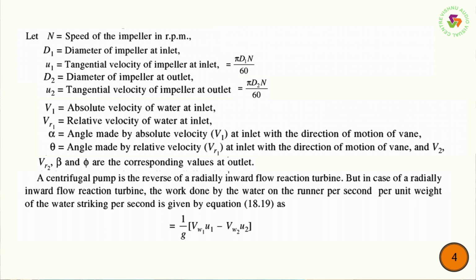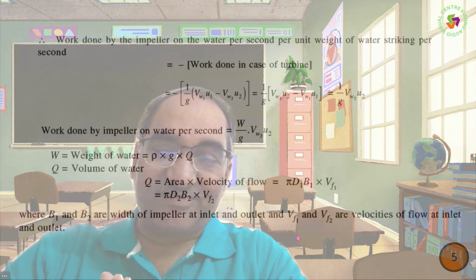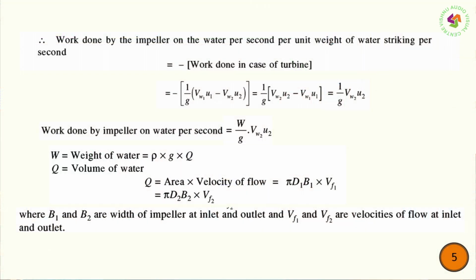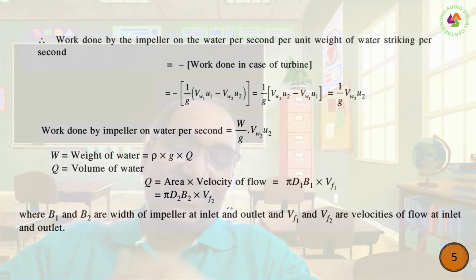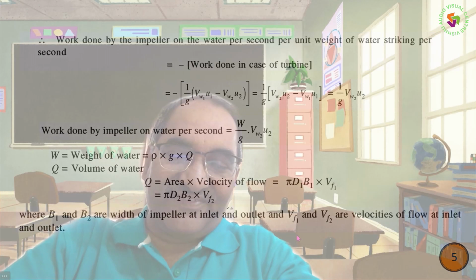The steps I have already explained. Please remember that in the suction pipe the pressure is always less than atmospheric pressure. It is vacuum pressure. How is the vacuum created? When you close the delivery valve and the impeller starts to rotate by the external motor, strong suction is created and it sucks the liquid from the sump, and energy is imparted to the water.